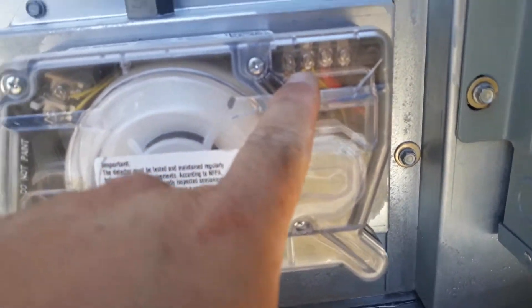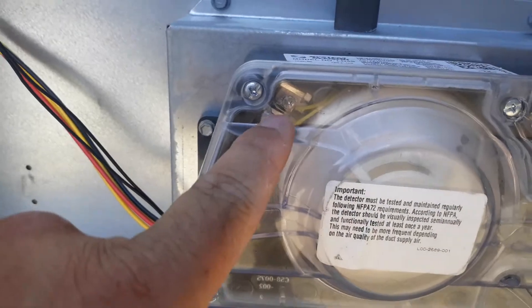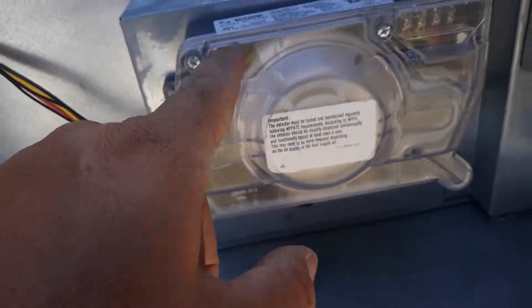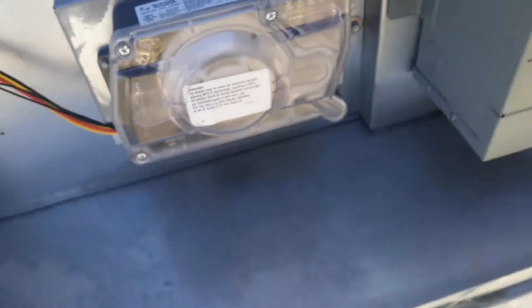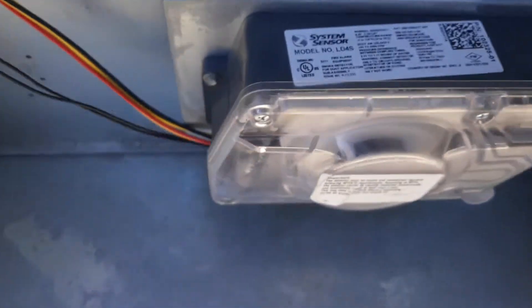See how it's got the yellow wires right there. You trace them out — they come over here to this little switch, which is a normally closed switch. So whenever that screw goes in it closes that switch. Or if the heads are moved, it'll kick a supervisory as well.